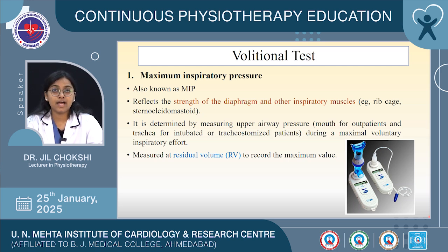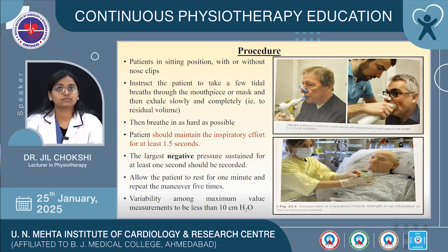Residual volume means the air that remains in the lung after forceful expiration. For performing this maneuver, patient is in a sitting position with or without using the nose clip. You have to instruct the patient to take a few tidal breaths through the mouthpiece or mask and then exhale slowly and completely to the residual volume. Then you have to instruct the patient to breathe in as hard as possible and maintain the inspiratory effort for at least 1.5 seconds. The largest negative pressure that is sustained for at least 1 second should be recorded.